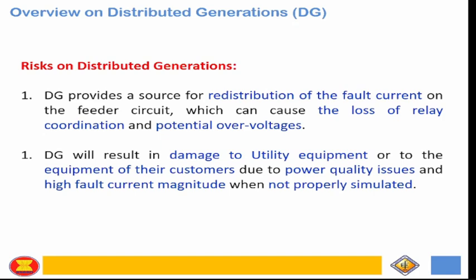So in our case, we implemented series inductors to somehow reduce the fault current. That's one way, like the NGR, the neutral ground reactor. So that may be the practical solution while replacing those fuses. Imagine replacing all of the fuses. That's why we need to properly simulate having that distributed generation. Okay, and also the power quality, as mentioned.